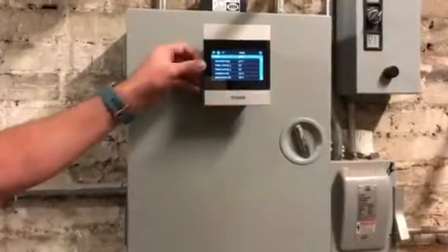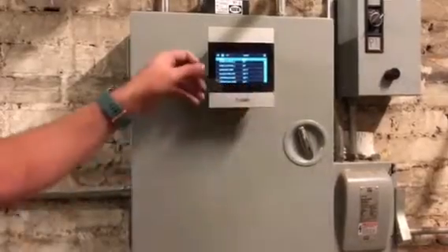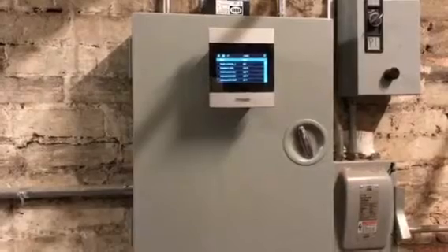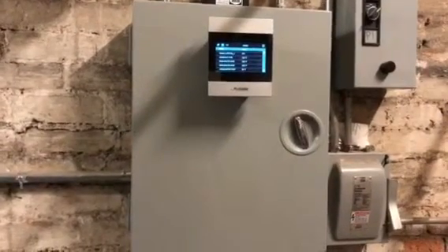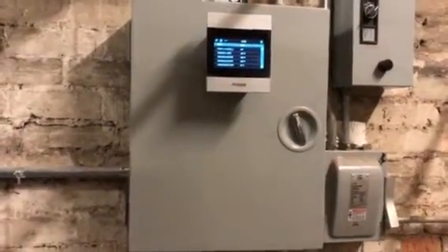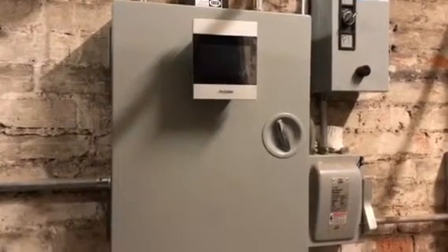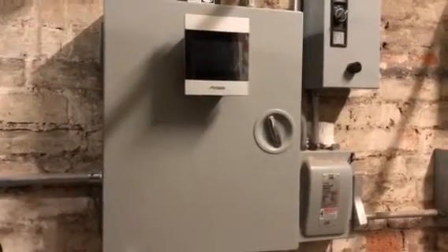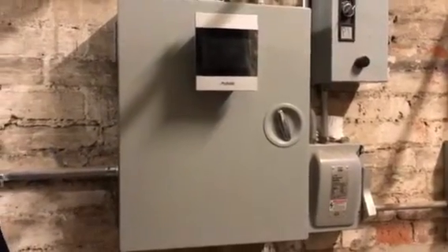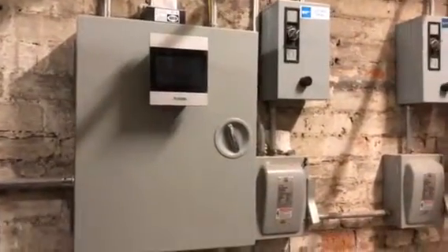Inside this room, pump statuses, and we're monitoring the domestic hot water system. On that hot water system, you're just monitoring. We're just monitoring domestic. Now, will that come across any type of errors or anything on the website? Yeah, I think I've got it set that if the domestic hot water supply temperature drops below 100 degrees, we send out an alarm. So we know that there's a problem with the boiler or a pump or something. So we are monitoring the domestic hot water. We are controlling the heating boilers.